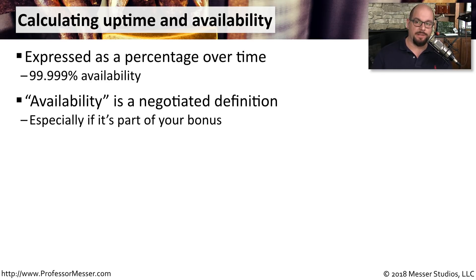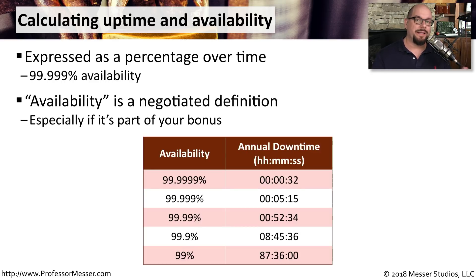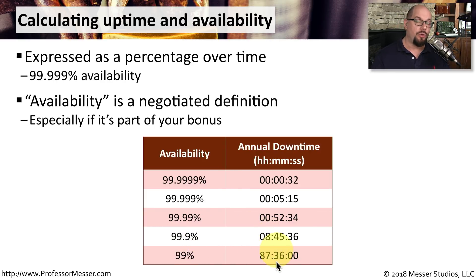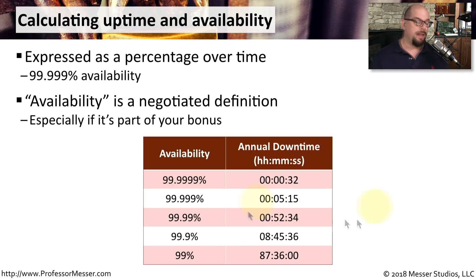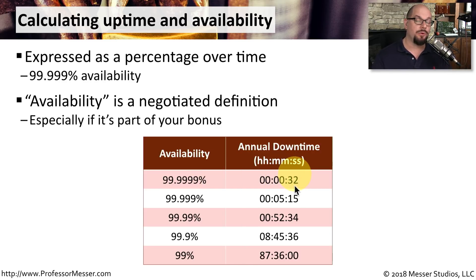These definitions are especially important if availability calculations are part of your salary or an ongoing bonus. Looking at an entire year, a 99% availability means you could be down for a total of 87 hours and 36 minutes. If it is four nines, you only have 52 minutes and 34 seconds of downtime. And if you're working on six nines — 99.9999% availability — your annual downtime cannot exceed 32 seconds.